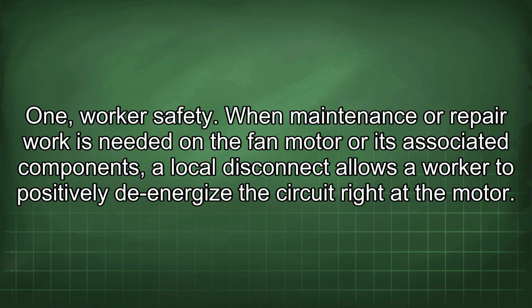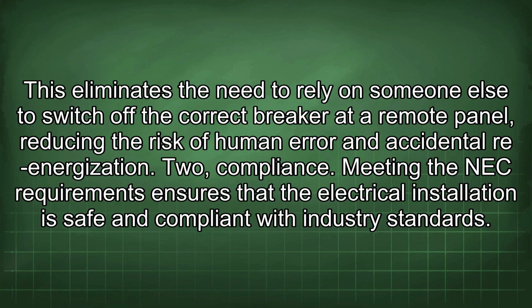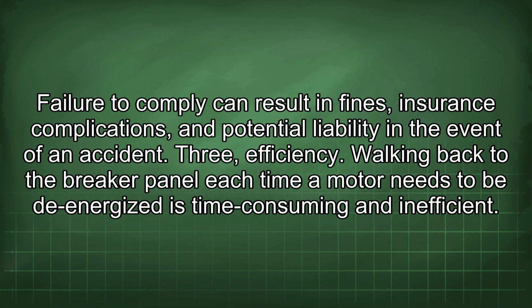1. Worker safety. When maintenance or repair work is needed on the fan motor or its associated components, a local disconnect allows a worker to positively de-energize the circuit right at the motor. This eliminates the need to rely on someone else to switch off the correct breaker at the remote panel, reducing the risk of human error and accidental re-energization. 2. Compliance. Meeting the NEC requirements ensures that the electrical installation is safer and compliant with industry standards. Failure to comply can result in fines, insurance complications, and potential liability in the event of an accident.